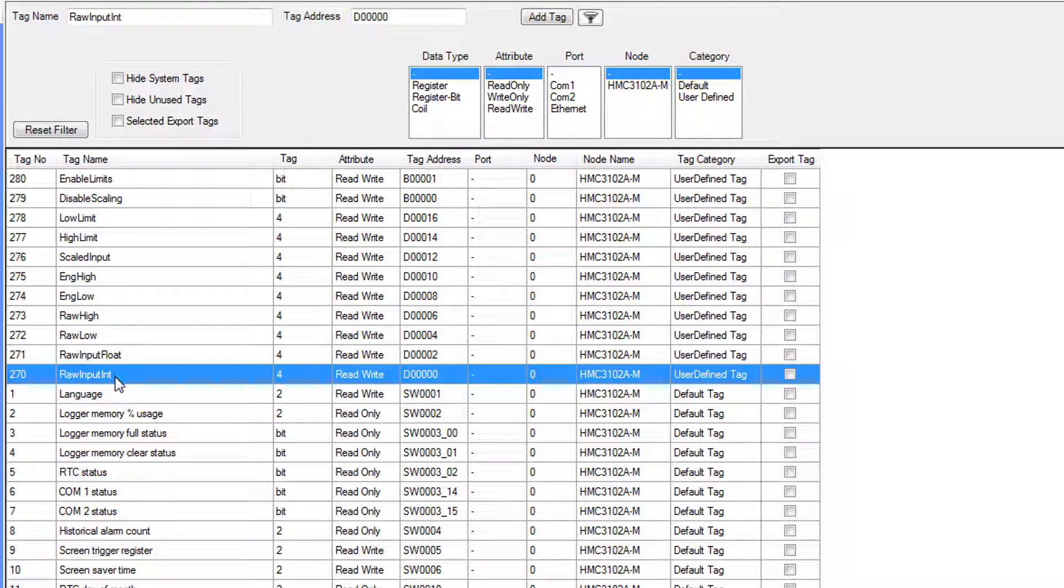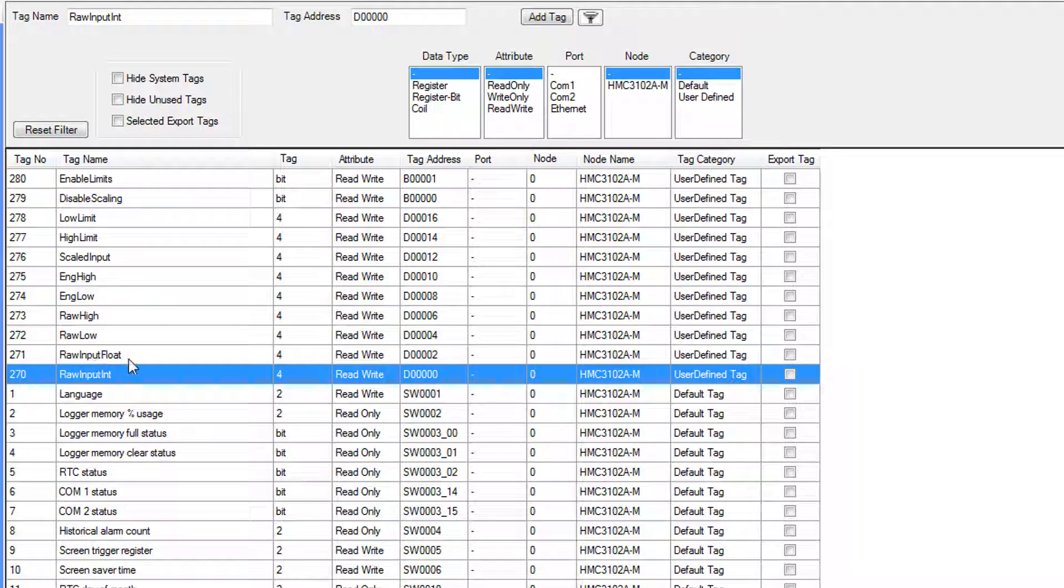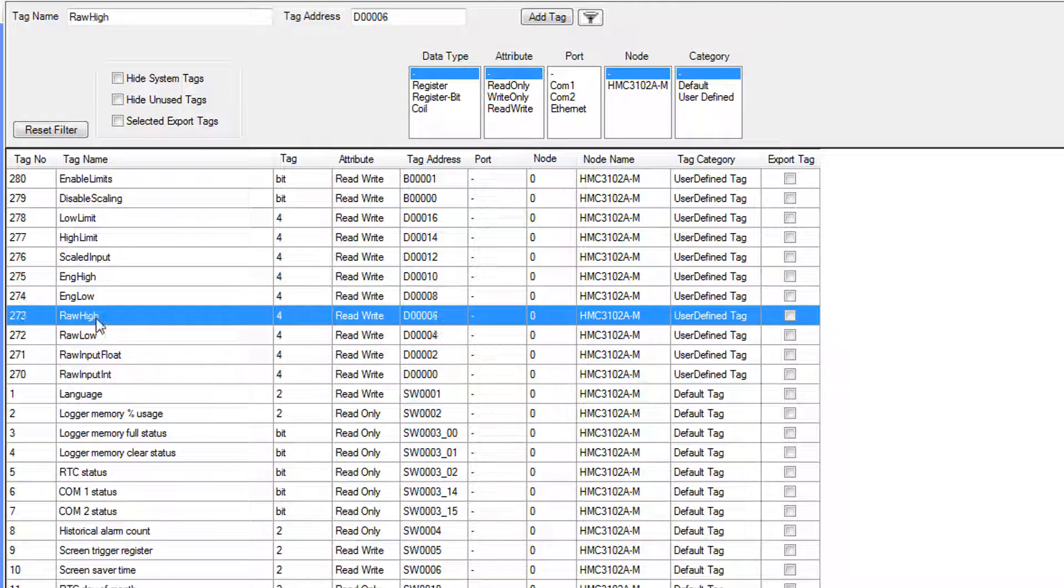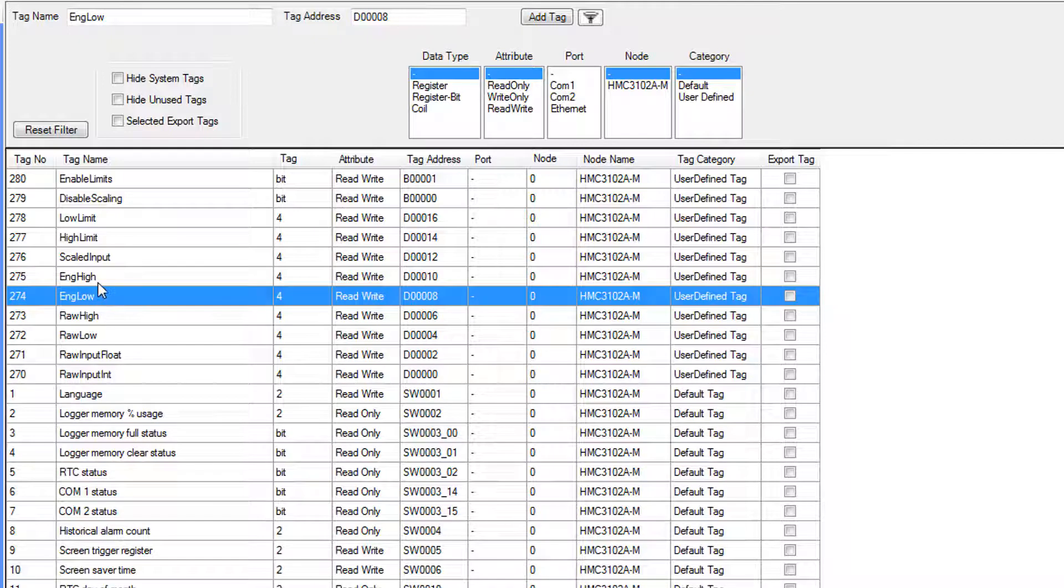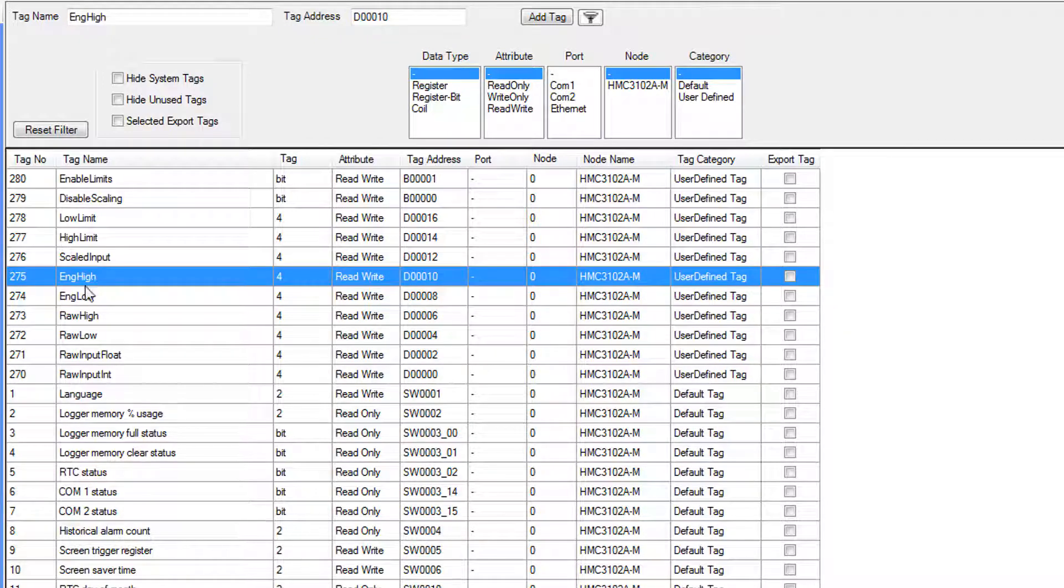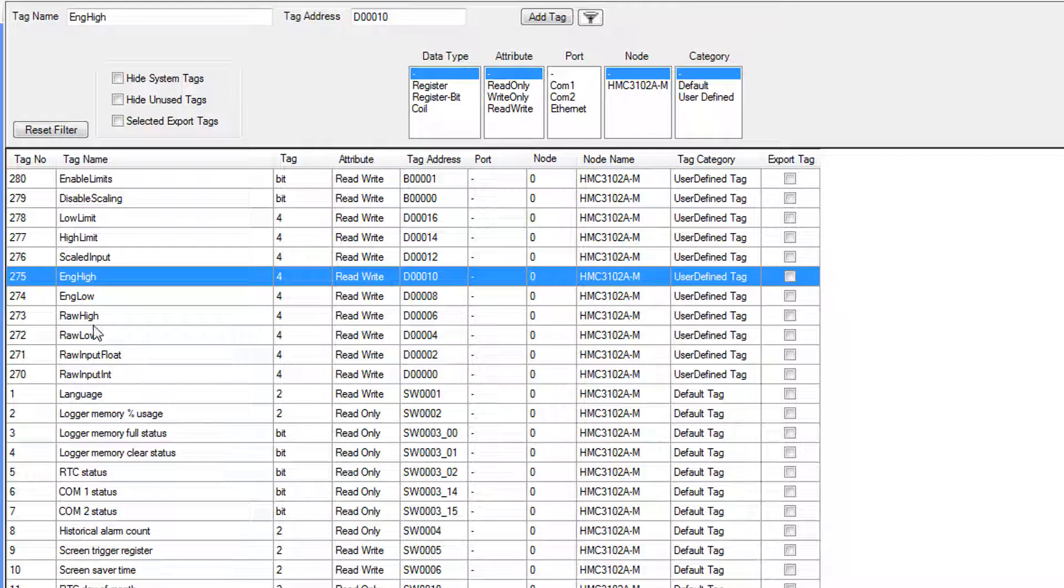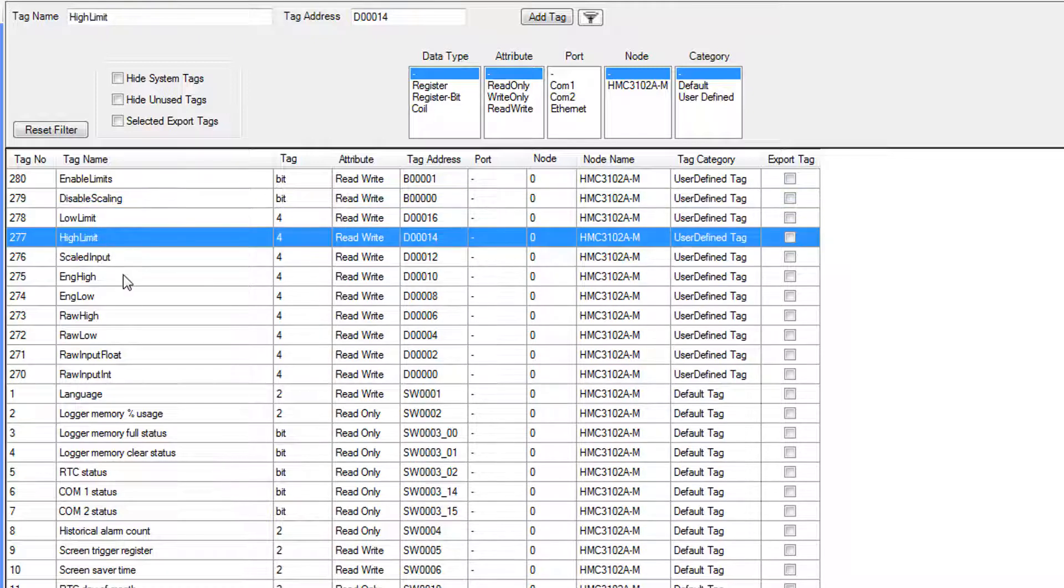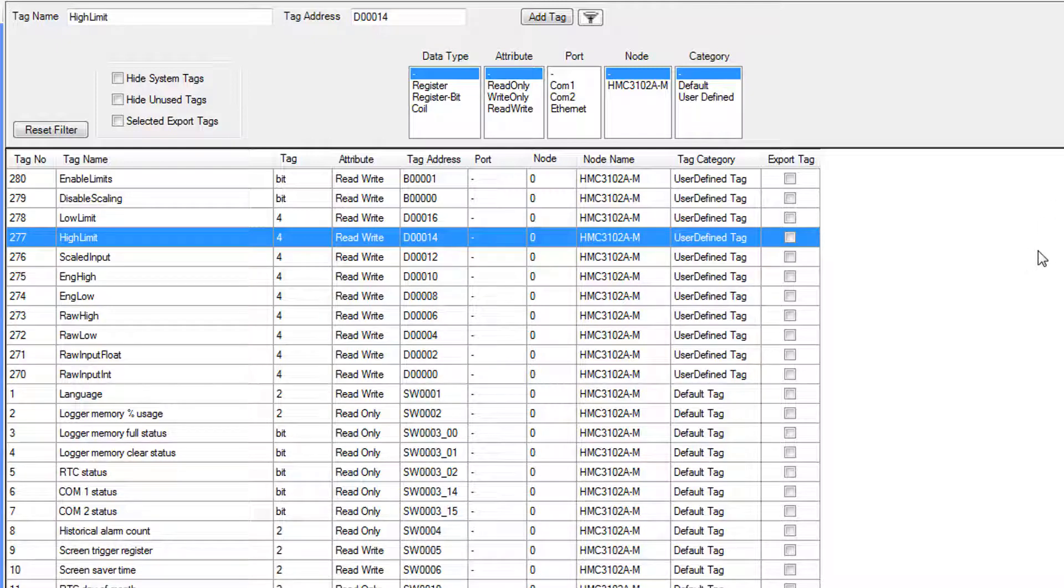RawInputInt is going to hold the raw input data, and we're going to convert that raw data into a floating point number. These next four tags are going to be used in the scaling function. RawLow is the lowest value that the input can be, and RawHigh is the highest input value. EngineeringLow and EngineeringHigh will be the range that we're going to be scaling it to, so input range, output range. ScaledInput is going to be that output from the scaling function. The highLimit and lowLimit are going to determine whether or not our input that we're getting is within a predefined range.